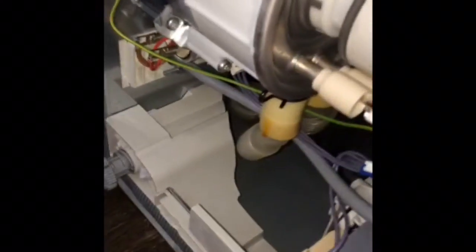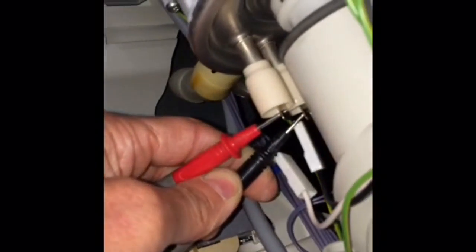We're just going to test it for continuity to make sure that it's not the heater, but the heater relay. So checking it for continuity, it shows 11 ohms. So we know the heater is okay.